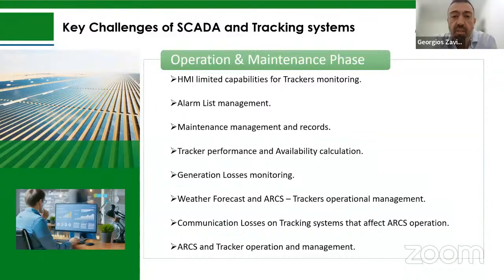Taking all this into perspective, from the developer's point of view, trying to optimize the vendors, in our case it's not the more the better, it's the less the better. In terms of vendor interfaces and integration, we see value in having a tracker supplier or vendor take under his umbrella management of all those signals, and the SCADA-related monitoring and controlling of the system. We see merit in that, and therefore we endorse and appreciate such effort.